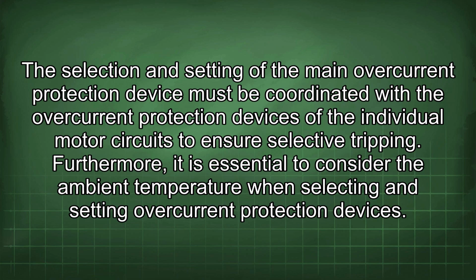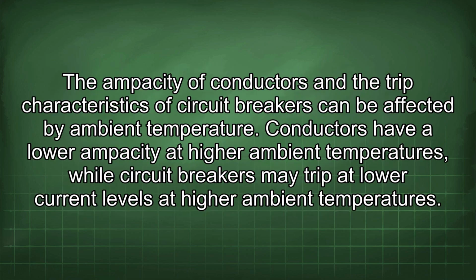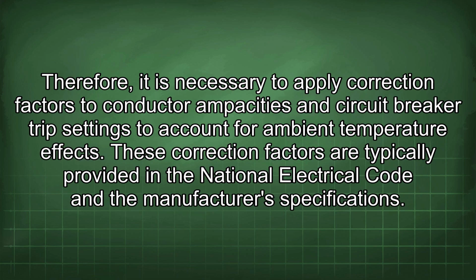Furthermore, it is essential to consider the ambient temperature when selecting and setting overcurrent protection devices. The ampacity of conductors and the trip characteristics of circuit breakers can be affected by ambient temperature. Conductors have a lower ampacity at higher ambient temperatures, while circuit breakers may trip at lower current levels at higher ambient temperatures. Therefore, it is necessary to apply correction factors to conductor ampacities and circuit breaker trip settings to account for ambient temperature effects. These correction factors are typically provided in the National Electrical Code and the manufacturer's specifications.